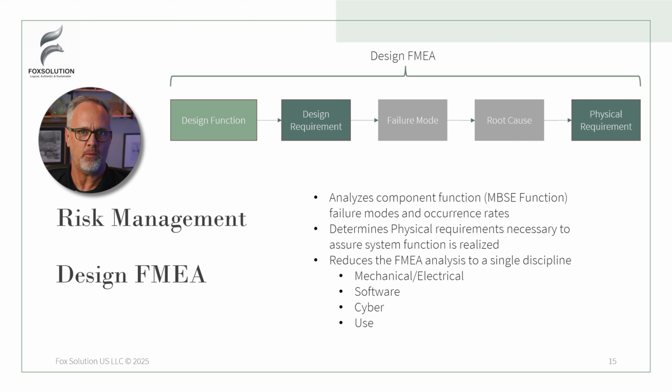So in this case, now we have a design requirement that we're going to analyze for failure modes and root causes driven from design functions that are delivered in one component of the system. Now, this is really necessary because those design requirements are related to different disciplines. Might be software, might be hardware, might be usability. This is where we've assigned it to a particular discipline, so we know which format of design failure mode analysis to put it through. And the reason I say that is when you do a software failure mode analysis, we don't have 20% failure. It either fails or it passes.